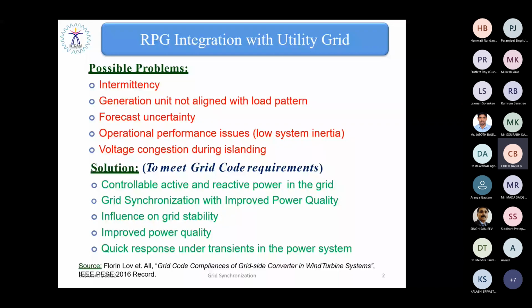For successful integration of a solar PV system, we have to meet the grid code requirements, which include grid synchronization. So we have taken an attempt and were able to develop a pre-filter based phase lock loop for perfect grid synchronization under different grid abnormalities. Integrating a solar PV or the inverter with the utility grid during grid abnormality is a difficult and challenging task, so we attempted to solve such grid abnormalities. We proposed a kind of pre-filter based phase lock loop that I am going to present for the next 2 hours.